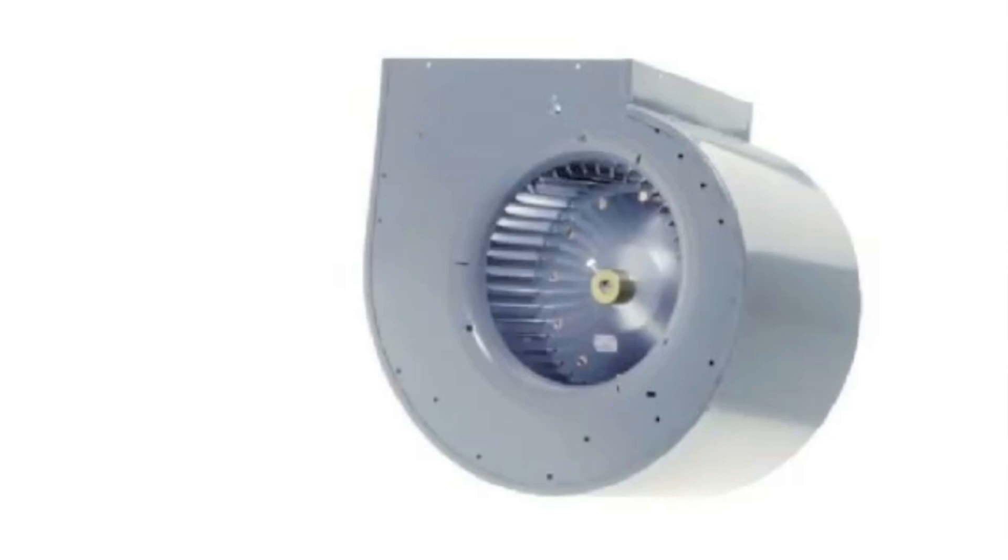Compare that to propeller type blowers - they won't work against hardly any static pressure at all. These blowers will - they can be made to work against whatever static pressure you want. But the squirrel cage blower is pretty much the air mover for most ductwork systems, unless you get to some very large axial type fans.